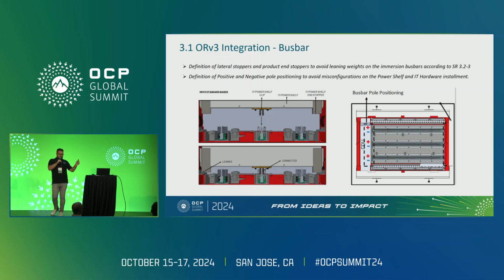This is an image you've probably seen before. Rolf made a very good point earlier about busbar polarity, another important point for how we install IT hardware and power shelves into immersion tanks, making sure the positive and negative are always on the same side. We're not frying any server or taking any risk by installing things improperly. There are also lateral stoppers, as we mentioned, to make sure the weight never relies on the busbar, but on the tank structure instead, so the busbar doesn't carry weight it wasn't designed for.